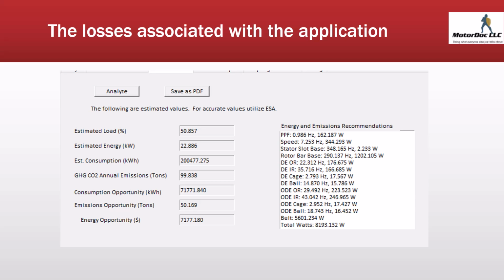And here is where we're taking a look at the total energy opportunity and the individual losses as we go through components. So the bearings, you can see inner and outer race have the higher losses on both ends, so that's a bad bearing. Now if I saw cage and ball as being higher losses but not the inner or outer race, then I would have looked at that as lubrication.